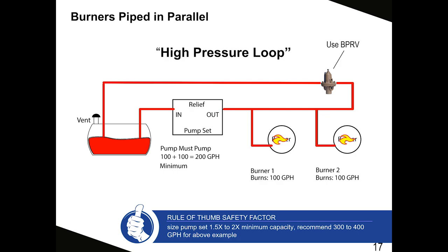So Ed, I wonder if anybody's asking, how come there isn't a return line off of those burners back to the oil tank? Well, since there are no pumps on there, we're not forcing more oil into the nozzle of the burner, so therefore there's no oil to be returned to the main fuel oil supply pipe. There are occasions, though, where they actually will put a scavenger pump on there, so when a burner is being pulled out of service, they can just pump the residual oil out of it.